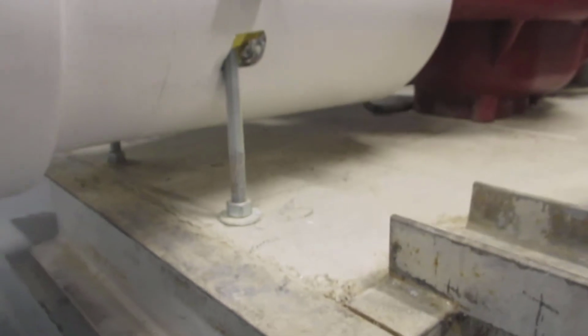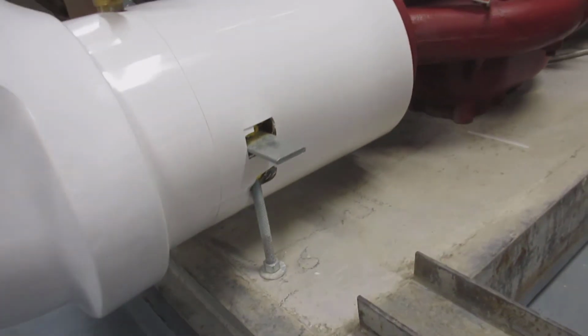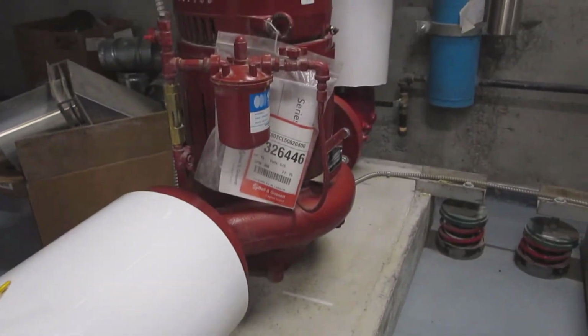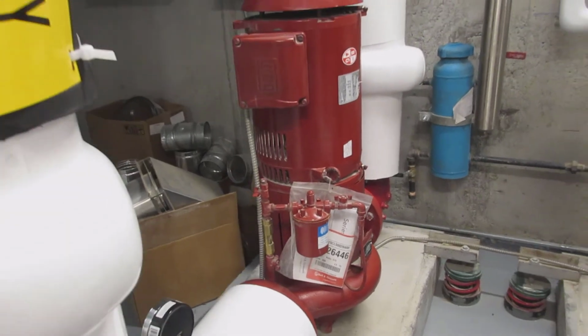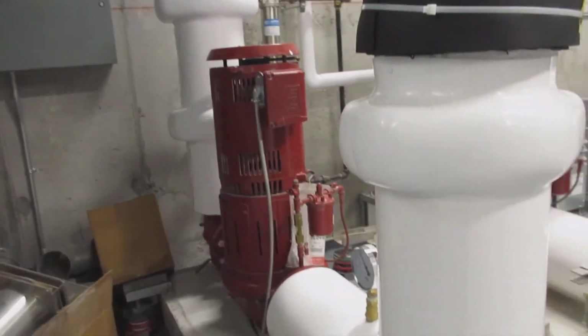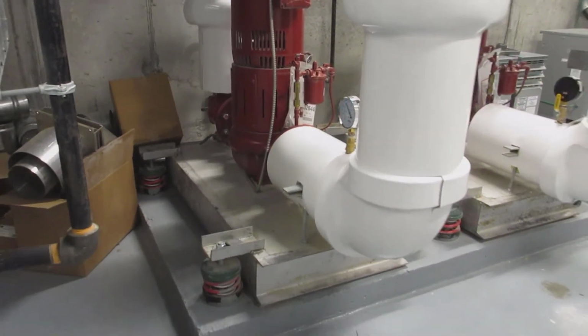Looking again under the first inertia base and then the second one, we see that here too the gap is much less than the 2 inches shown in our submittals, and there's some debris. Instead of using an inline pump stand or stanchion, the discharge elbow is supported with a pipe clamp and threaded rods anchored into the base. Coming around the discharge pipe, we can see the other side of the base and confirm the last 2 isolators installed similarly to the others.